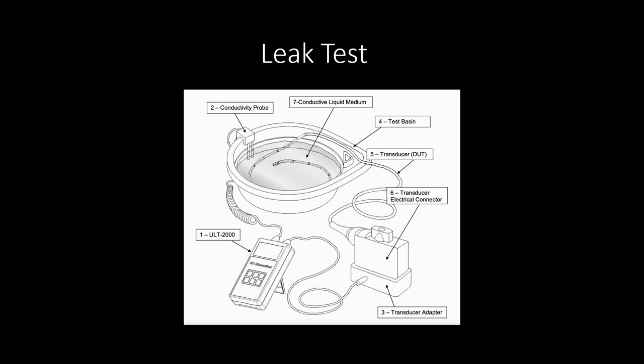So I went down and watched them, and I noticed that it's not snapping into the transducer adapter. And they're like, oh yeah, see, your probes are made by Mindray, and this is made by Philips. I'm like, they're not compatible, that's why. So all our probes were failing the leak test because they were using the wrong adapter. And they're like, well, you guys would have to buy that adapter. I'm like, yeah, it's like $3,000, right? You're failing these $35,000 probes because you don't know that you need a $3,000 adapter.